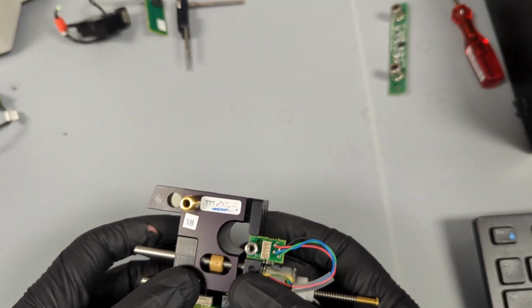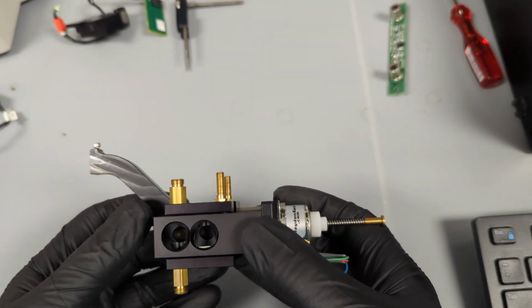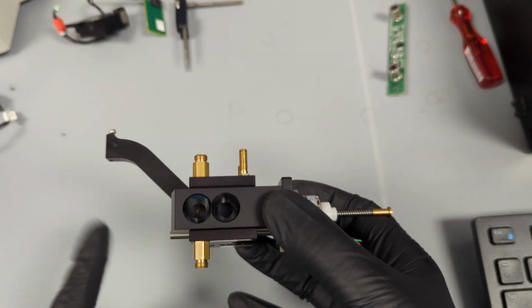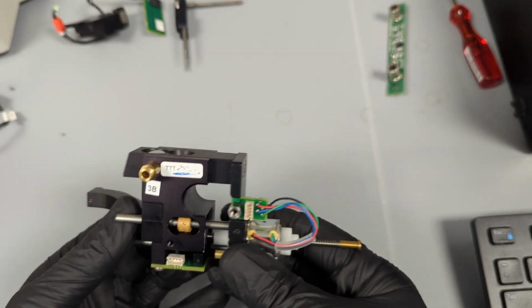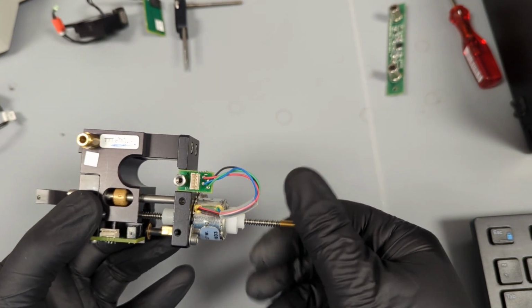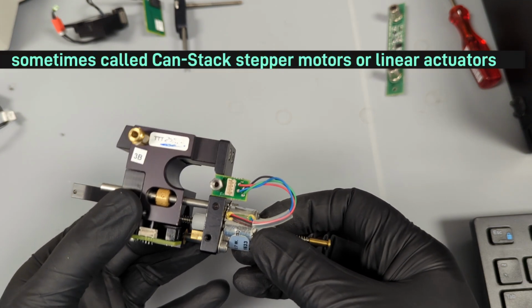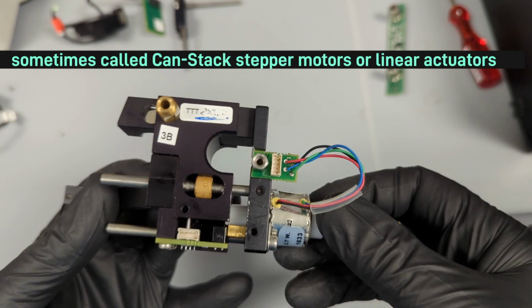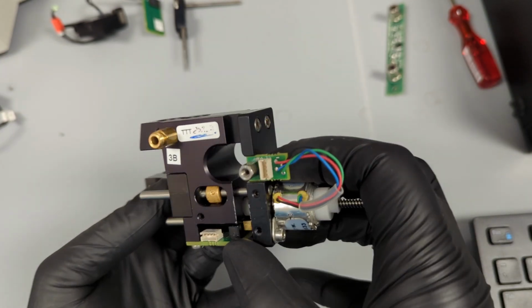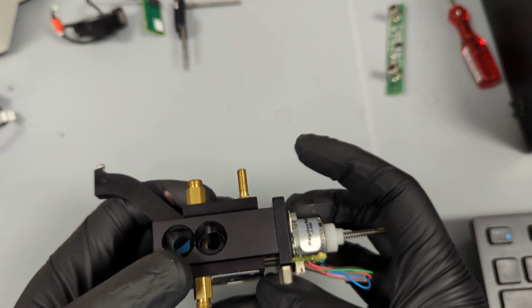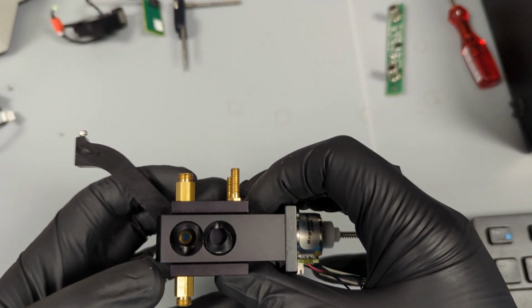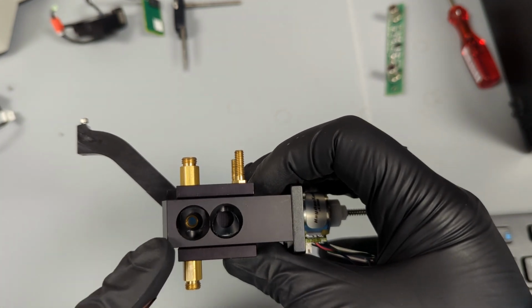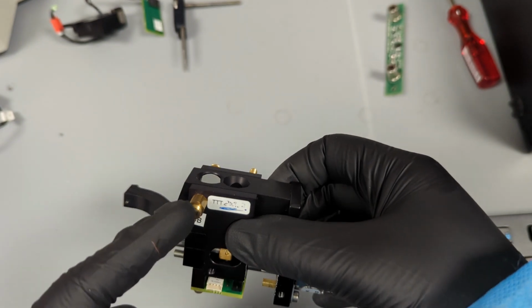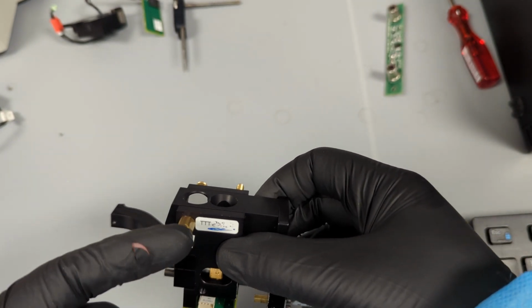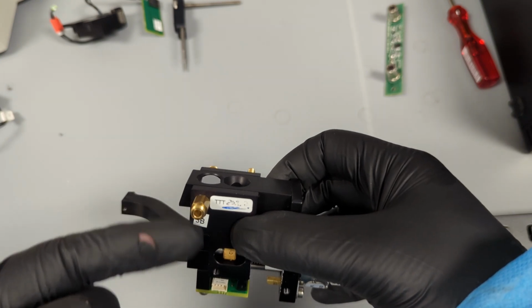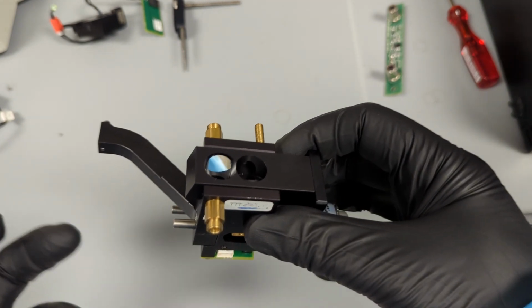So this is the excitation light selector, and this is just selecting which path the excitation light is going to take. It's being controlled by this stepper motor on this Acme style screw, so it can move back and forth, and then it can even home itself with this little actuator and this U-slotted photo microsensor. If you can see here, we've got some mirrors, so when it's in this position, it's kind of hard to tell, but you have a mirror here that's going to direct the light out this way where it says 3B, and then there's an optic cable that connects to the bottom read head, so you can take measurements from the bottom of the plate.